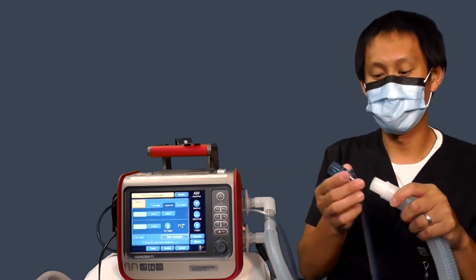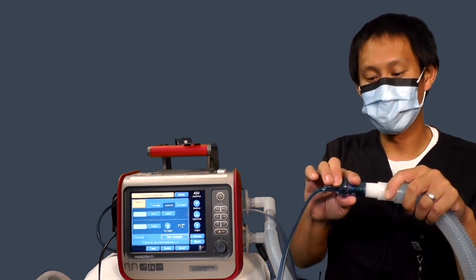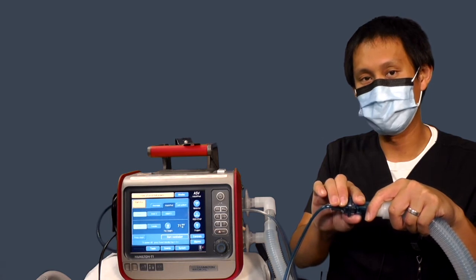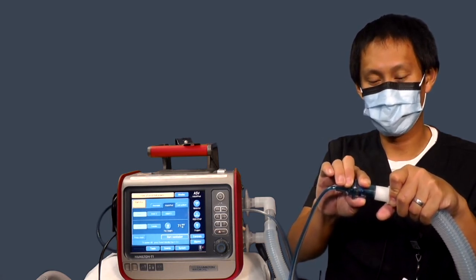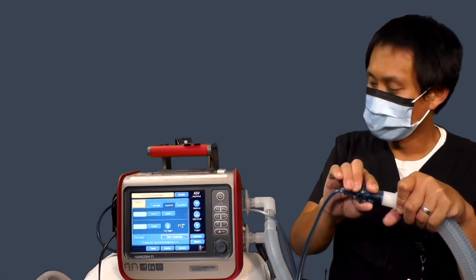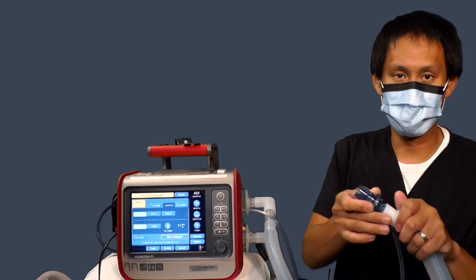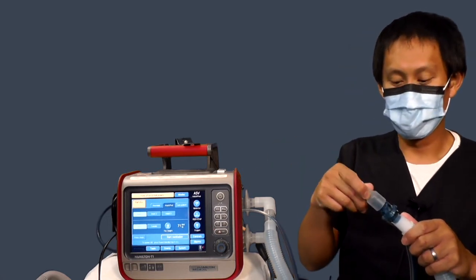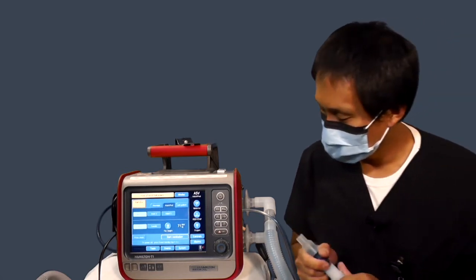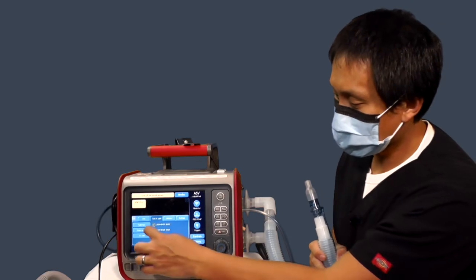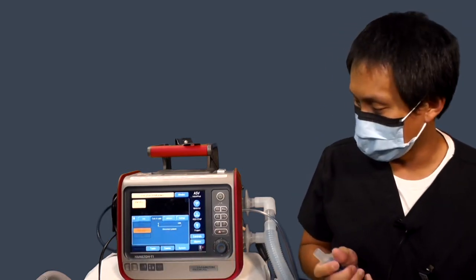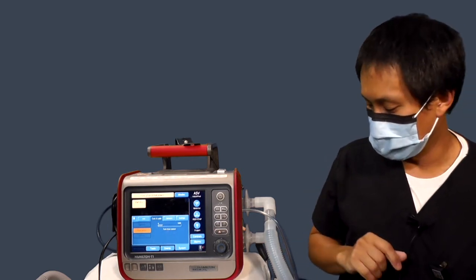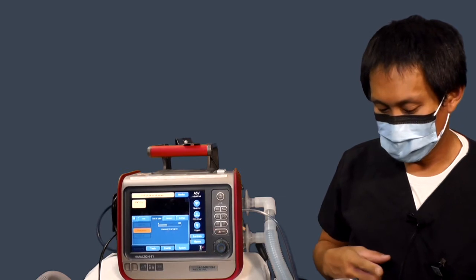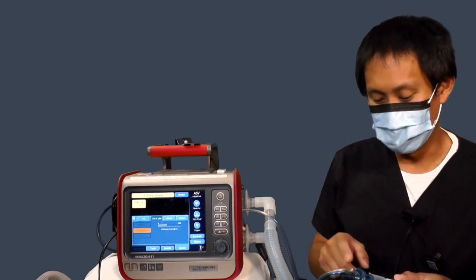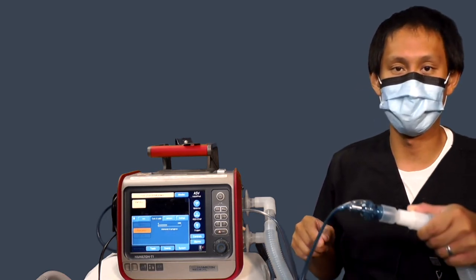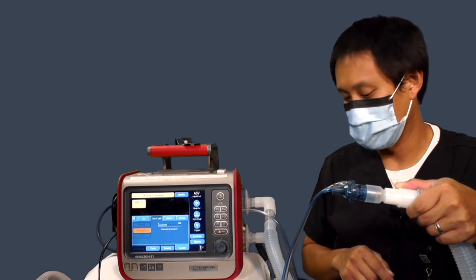what you'll need to do when it tells you to flip the flow sensor around is hold the flow sensor up tightly against the ventilator circuit, like so, until the duration of the test is over, or when the message tells you to flip it back around again. I'm going to demonstrate it using the adapter. So we'll go ahead and start this test. Disconnect from the patient, turn flow sensor, and then what it's doing is essentially shooting out flow through the circuit, and then it's measuring how much it's putting out versus what it's measuring. So that's how it calculates the flow sensor.